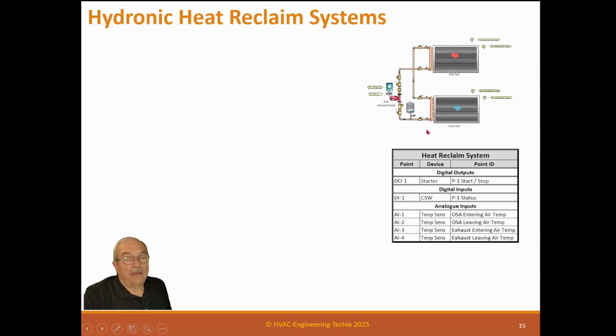If you're in cooling mode, then it takes the cold air and the cold water, it cools the water and runs it over and cools the outside intake air. So it's vice versa. Depends on which one's higher or colder. Points are pretty simple. P1 starts and stops this pump. Digital inputs, the pump status. Analog temperatures: outside air entering air temperature, outside air leaving temperature. And then we put an exhaust air entering air temperature, and exhaust leaving temperature.